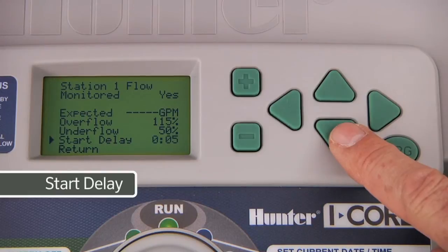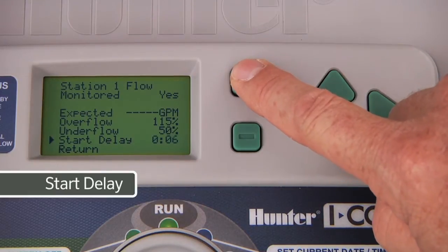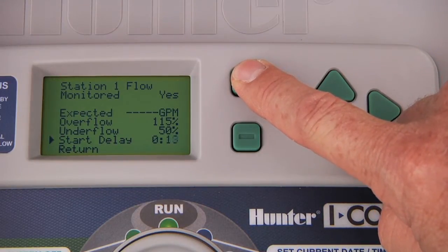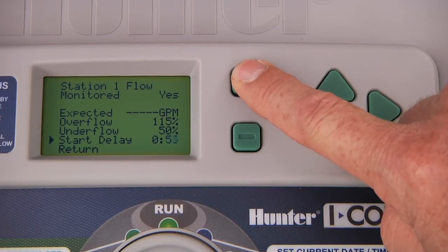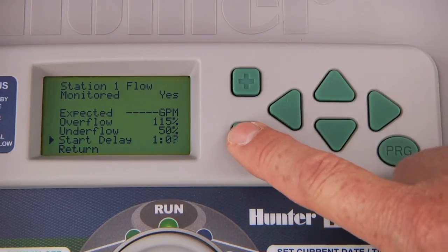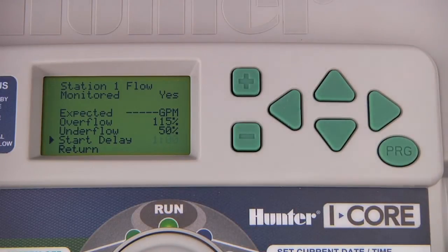The start delay is a period of time that is programmed to allow the system to stabilize in case there was unstable flow within the main line after turning on that station. The default is 1 minute, which means that flow will be ignored for alarm purposes for the first minute after a station turns on. If an underflow or overflow condition continues to be recorded past the 1 minute delay, then the controller will shut down that station.